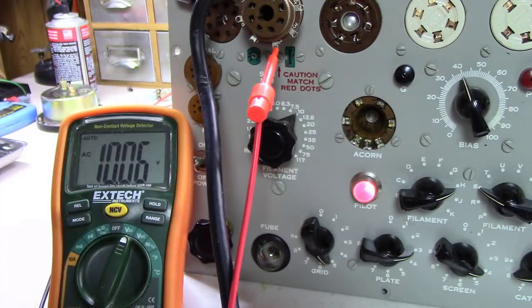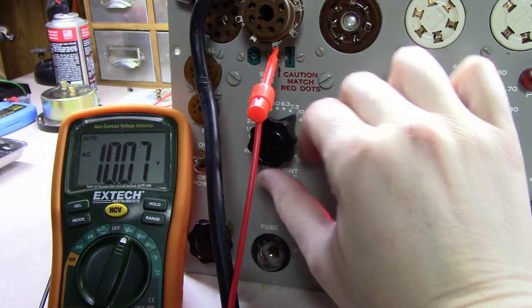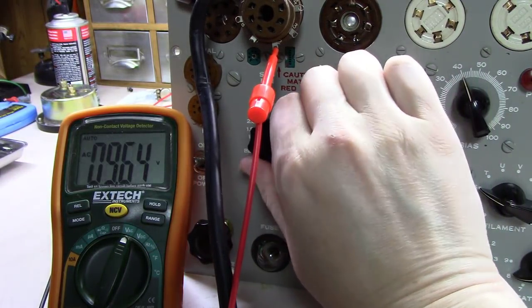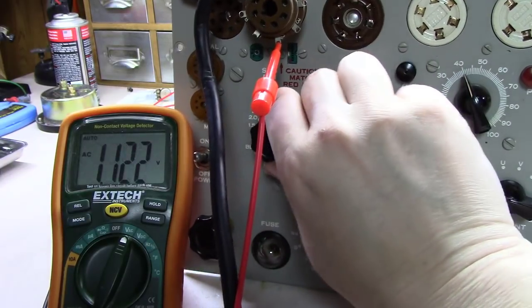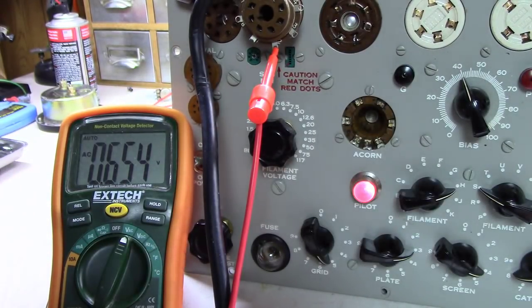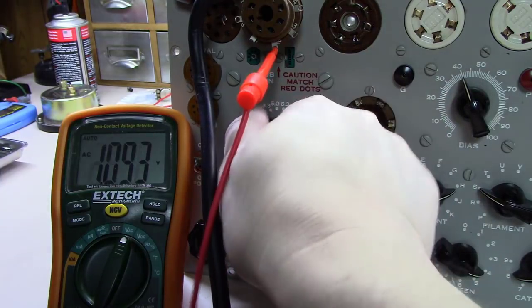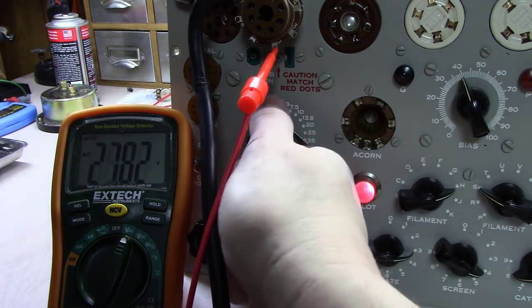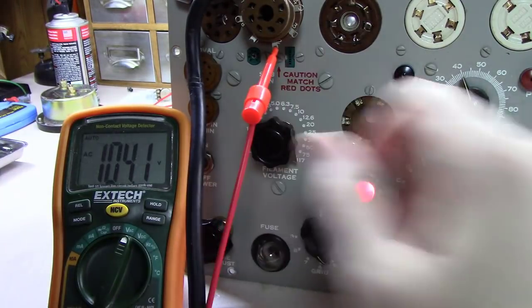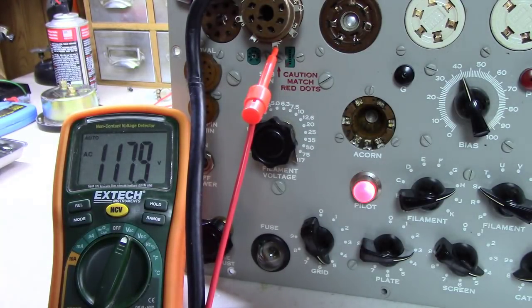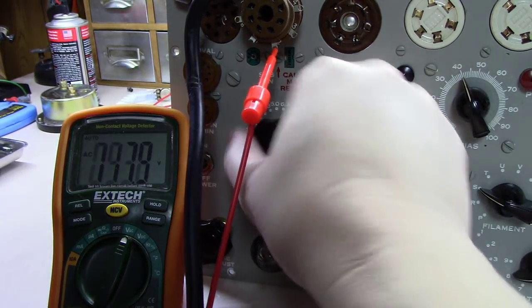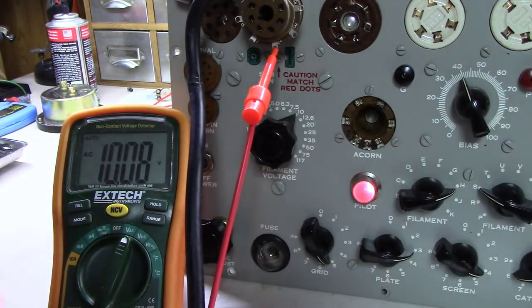Okay, if you'll notice, we're still here at 10.06, 10.07. I'm going to adjust this now down to the 0.6 range. And you'll notice we're at 0.654, which is pretty darn spot on. And then if we take it all the way over here to 117 volts, whoops, you notice we're at 117.9. You could adjust it to get it exactly on 117. But then your 10 might be down just a little bit.